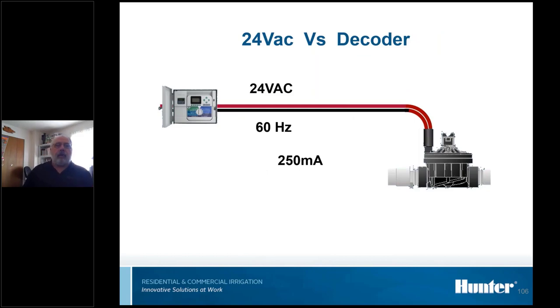So here's one of the other big differences. On a conventional system, we send 24 volts out the wire path, turns that solenoid on, and it draws about 250 milliamps or a quarter of an amp. Hunter solenoids tend to be a little bit lower than that. They're usually closer to 200, but we still call them 250.